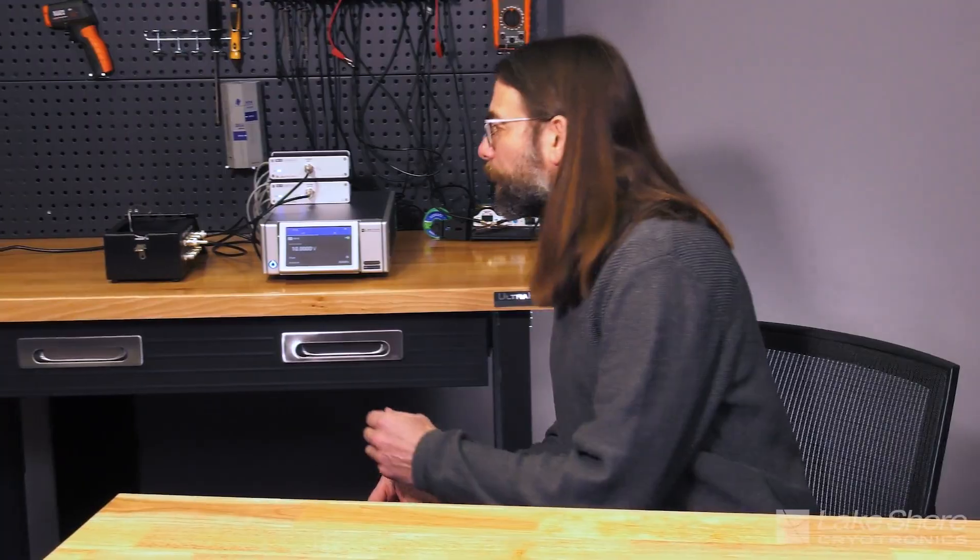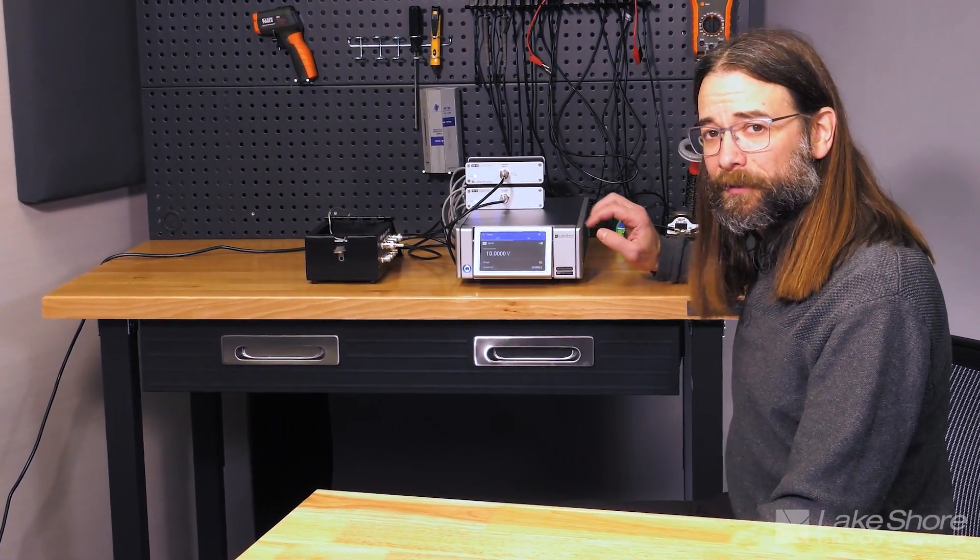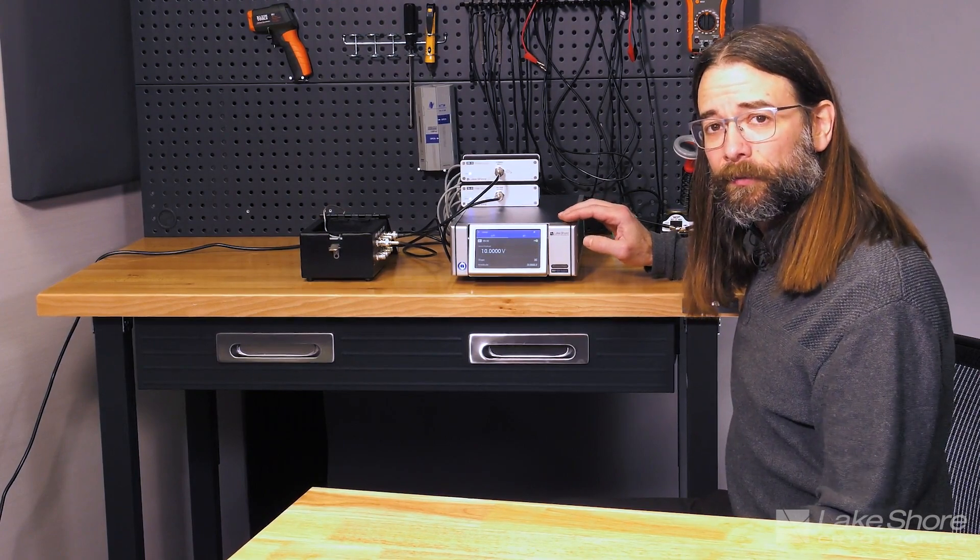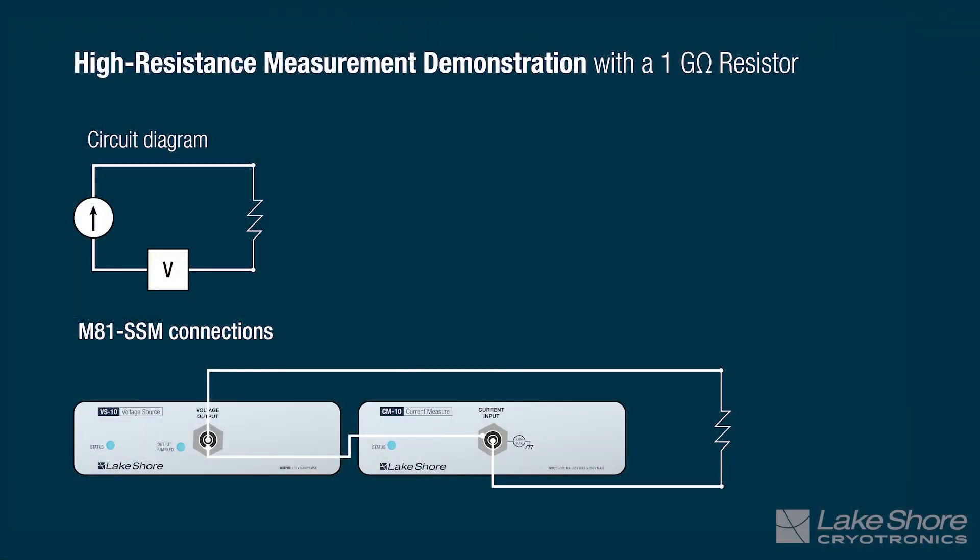So now let's take a look at the setup for this high resistance measurement. What we've got is the Lakeshore M81. This is our synchronized source measure unit. It's capable of sourcing current voltage as well as measuring current or voltage in both DC and lock-in. In this particular case we're going to look at a 1 gigaohm resistor in our test box. We've got a voltage output or voltage source the VS10 and then we've also got a current measurement module that's the CM10.